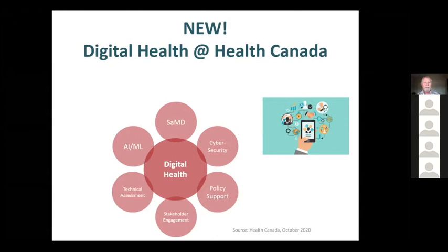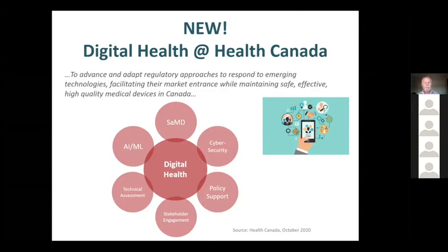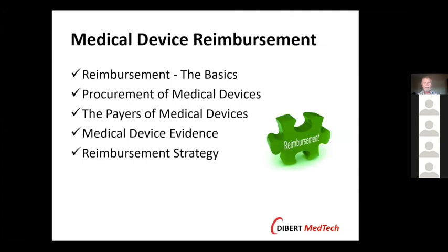So basically, digital health technology will be considered a medical device if it does what a medical device does. That is, it treats, diagnoses, mitigates, et cetera. So if it's covered under the same definition, Health Canada's definition for a medical device, it's covered.